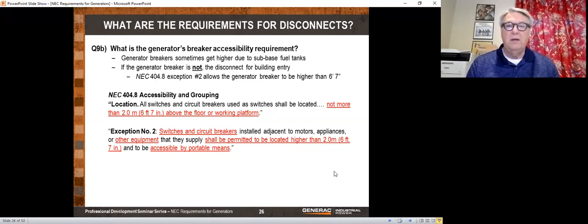Well, it turns out that it is okay, because there's an exception there. It says switches and circuit breakers installed adjacent to motors, appliances, or other equipment that they supply shall be permitted to be located higher than 6 foot 7 inches and to be accessible by portable means. So with Generac, we've tried to reduce the level in the generator at which we mount those circuit breakers, to try to keep them in a position where you can reach them. But it's still possible when you get a really large generator with a high tank, you may not, and that's fine.